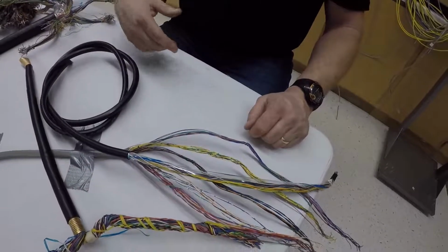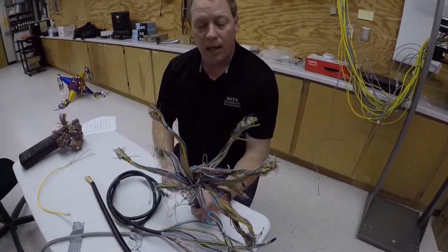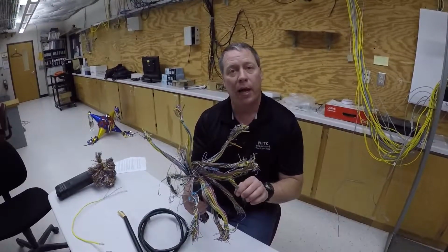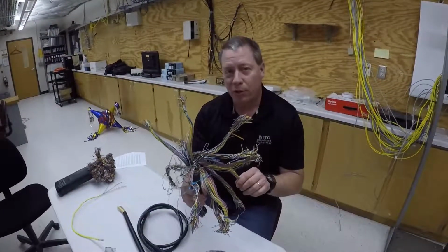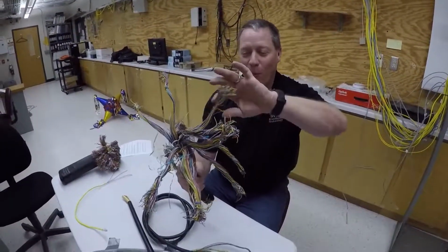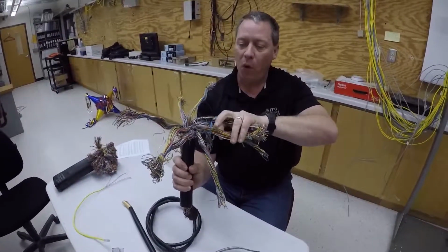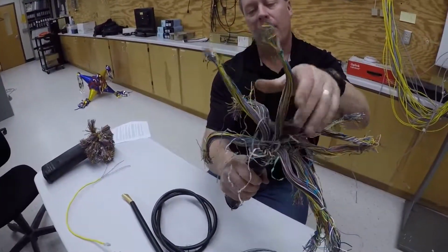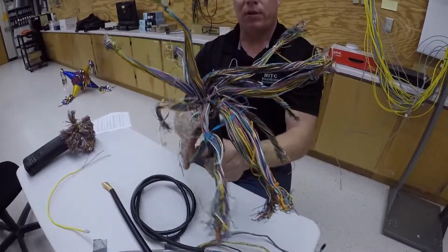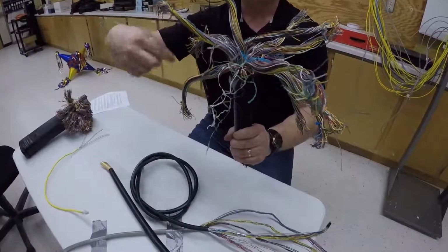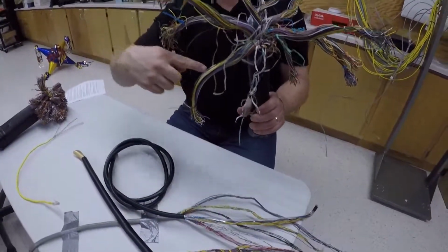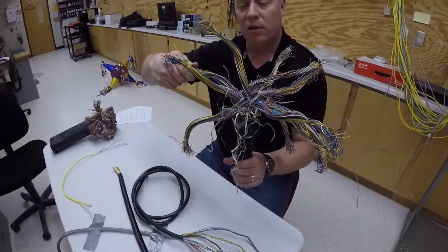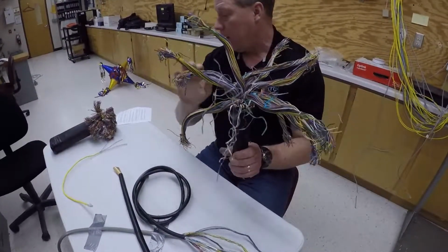Now when you get into high cable counts, for example, this one here is a 300 pair cable. So with 300 pairs, how many binder groups do we have? That's right, 12. And here we go. 1, 2, 3, 4, 5, 6, 7, 8, 9, 10, 11, 12. Now this one's been used a little bit, and our little binder ribbons are kind of straight all over, but just like in this one, you'd have each one of these binders wrapped in their color designated for that 25 pairs of cable, binder groups.